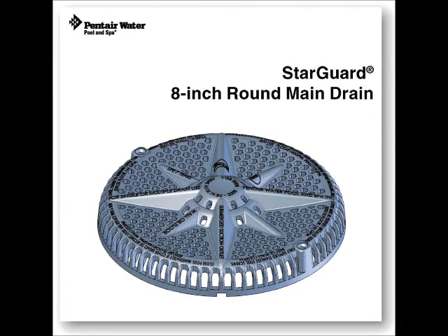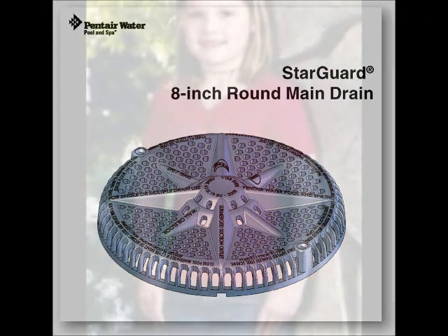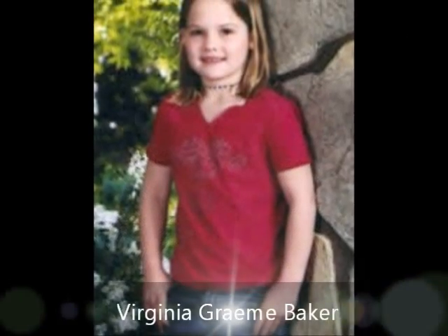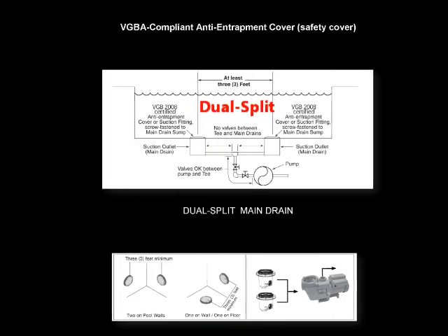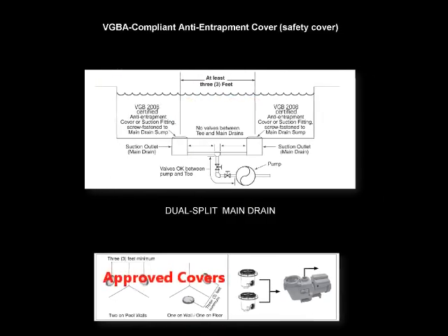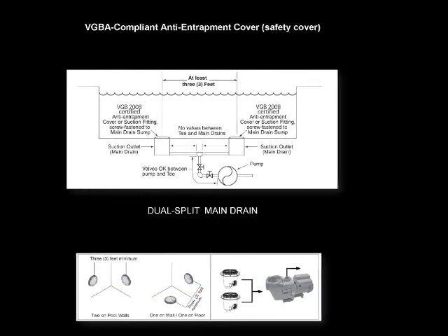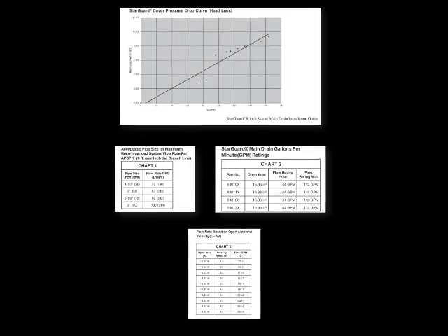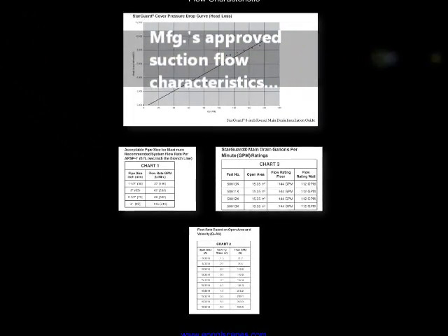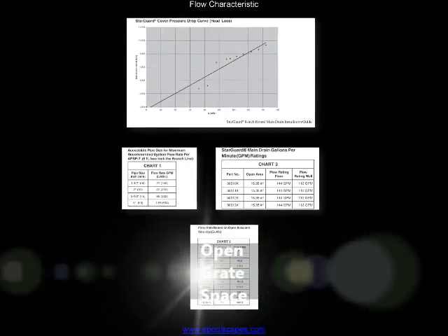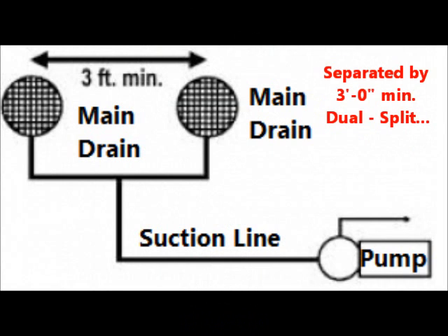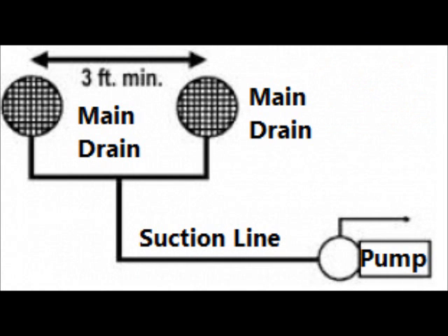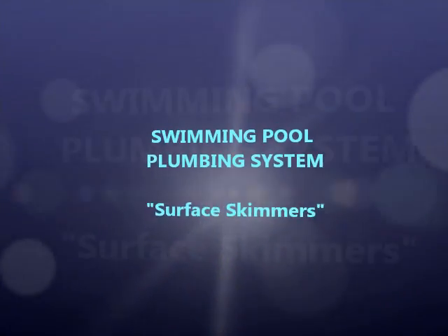After a young girl named Virginia Graeme Baker had drowned in a hot tub by being trapped on a defective main drain cover, an act was passed that now mandates that all suction inlets entering a swimming pool shell must be outfitted with an approved safety cover that correlates with the suction flow characteristic for open grate space per the manufacturer's published values. Additionally, these devices must also be plumbed into a dual split conformity separated by a three-foot minimum distance.